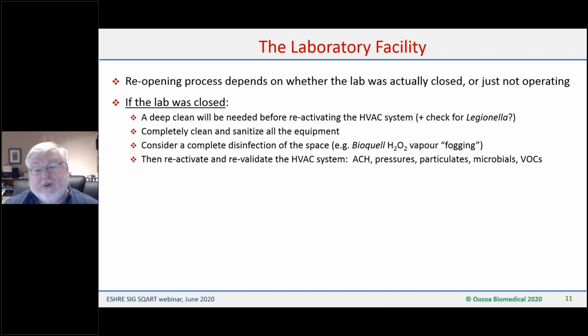Some people are talking about using Bioquell, which is a hydrogen peroxide vapor fogging of the entire space. Only after you know the place is clean can you reactivate and then revalidate the HVAC system. So if it's been turned off, it's going to have to go through the whole process of measuring air changes per hour, pressure differentials, particulates, microbials, and VOCs all over again.